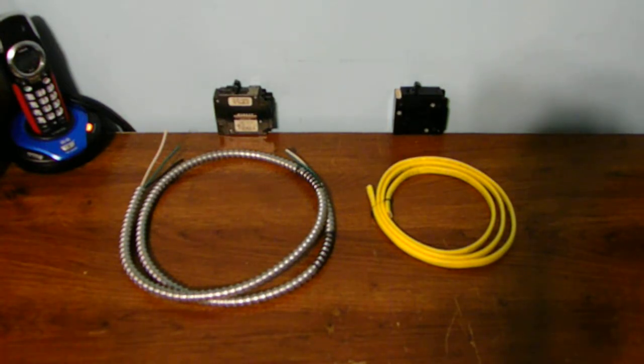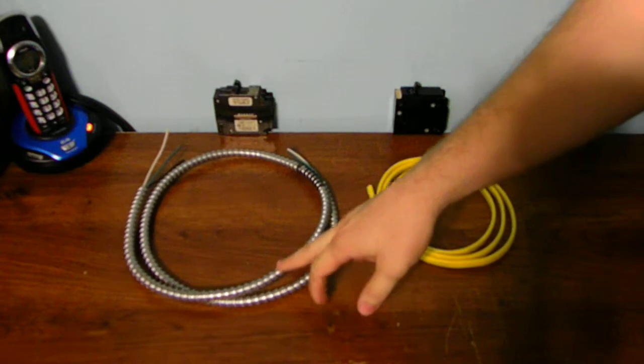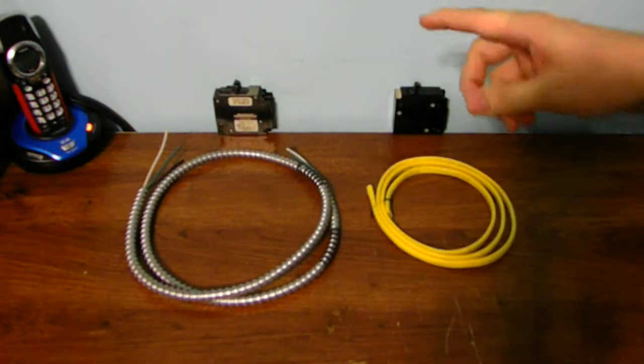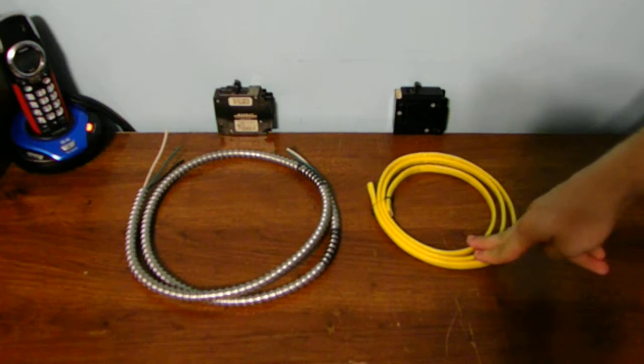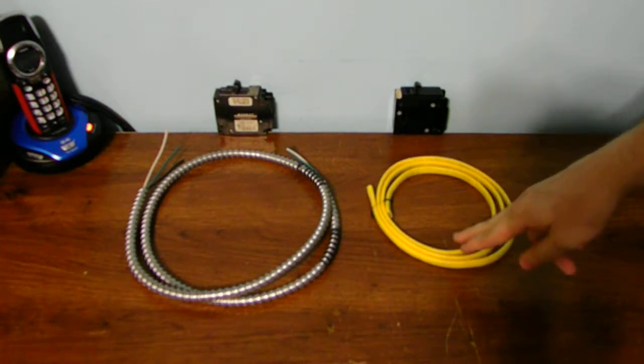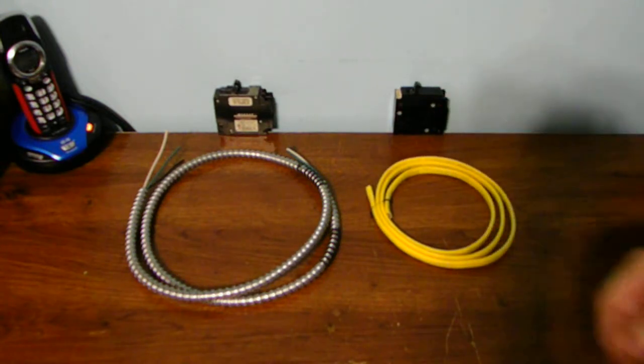The reason I have these two different cables is that one is more expensive than the other. You pay a bit more for the armored style cable versus the Romex style cable, but they do the exact same thing. This one is the armored cable, it has two conductors and one ground, 14 gauge wire. The Romex cable here is 12-2 gauge wire, two conductors and one ground.